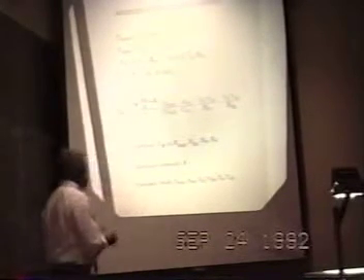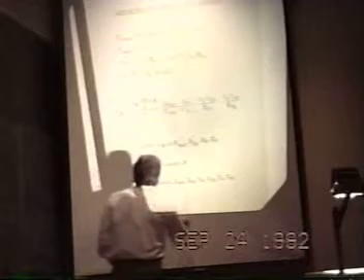The calibration constant, the conductive loss term from the calorimeter, which is a small term, but one which is calibrated at the beginning of the experiment and repeatedly calibrated throughout an experiment. And the variables that are measured: the mass flow rate, the resistance of the inlet and outlet temperature sensors, and the 4 voltages. We're looking for potential sources of systematic error in these terms.